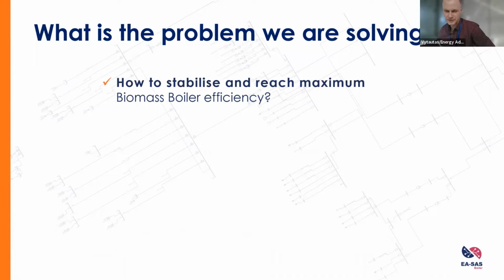What does efficiency mean? It's the ratio of produced thermal energy divided by consumed fuel, for example in megawatt hours. We always have a theoretical maximum that we can achieve, but due to operation issues, fluctuation of load, change of fuel and many other reasons, efficiency is not stable. And if efficiency is not stable, we burn extra fuel, and then we lose money.